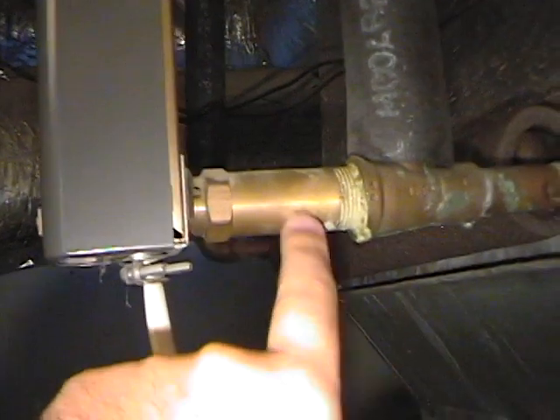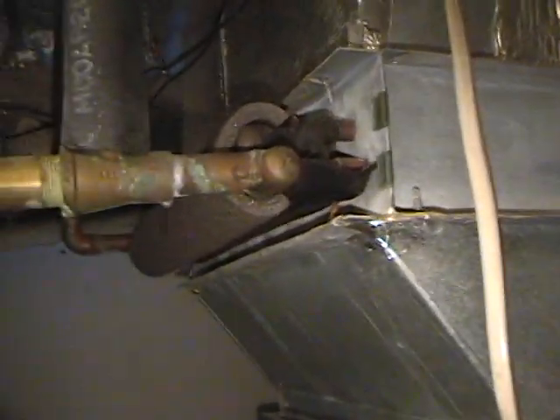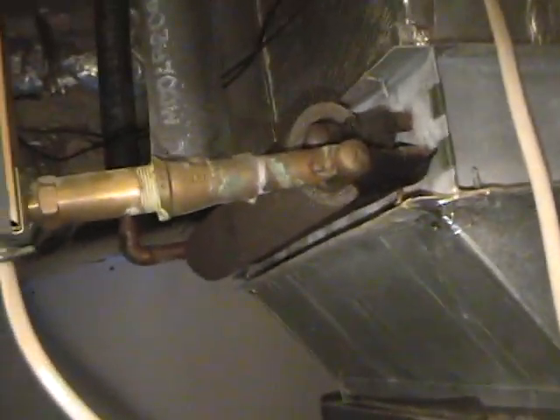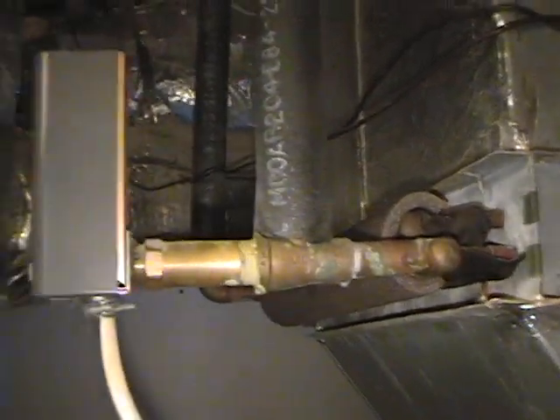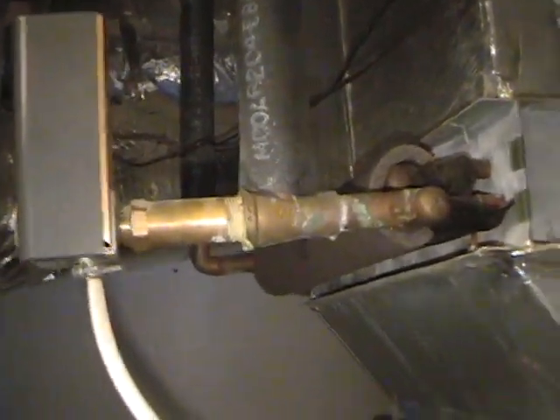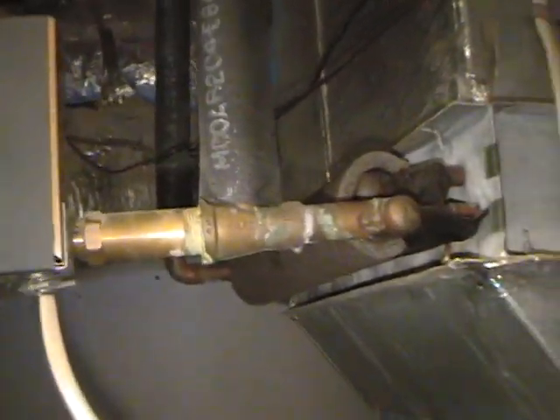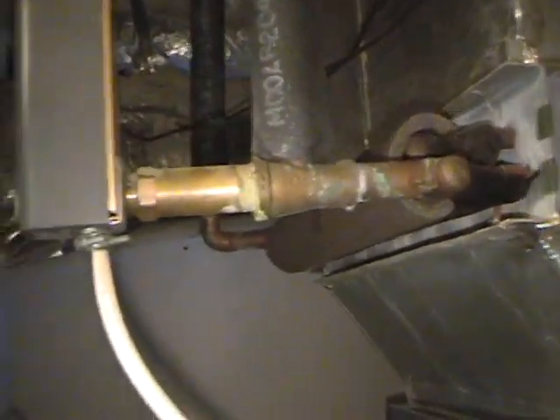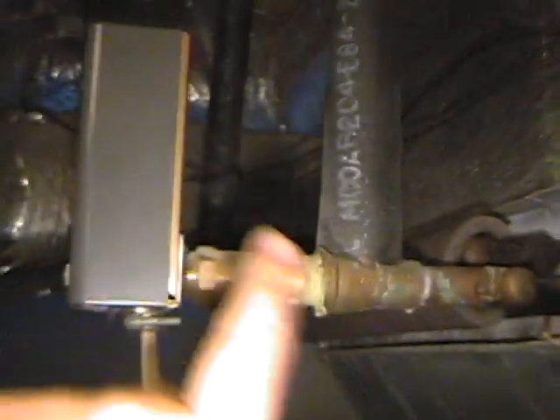And this little thermostat right here, this is what detects how hot the water is as it's going through the heat exchanger. So when the water gets to a certain temperature, it'll click on and allow the fan for the air handler to turn on. And then once the boiler shuts off, when the thermostat is satisfied, the fan will continue to run until this cools down enough to turn it off.